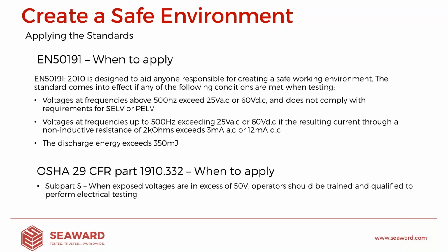Essentially what that's saying is, could that current flow through a human being? Typically, if we have an operator there, then the chance is yes, we could be exposing our operators to that level of voltage. And ultimately, could that current exceed either 3 milliamps AC or 12 milliamps DC? Now, again, it's true to say that a lot of production line testers are capable of currents far exceeding 3 milliamps AC. Some go up as high as 100, 200 milliamps AC. So if you have that level of tester, then you need to consider the safety aspects of it.